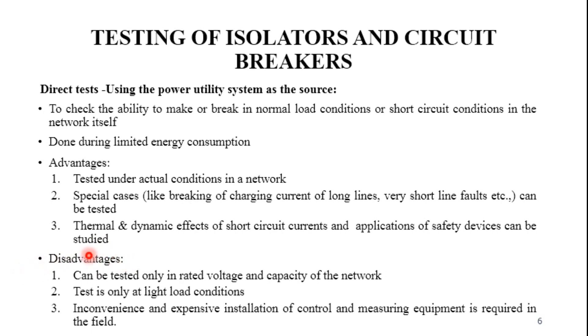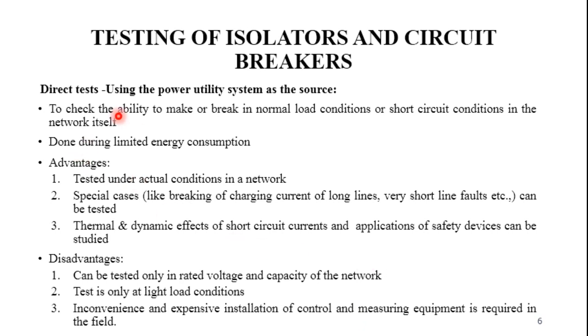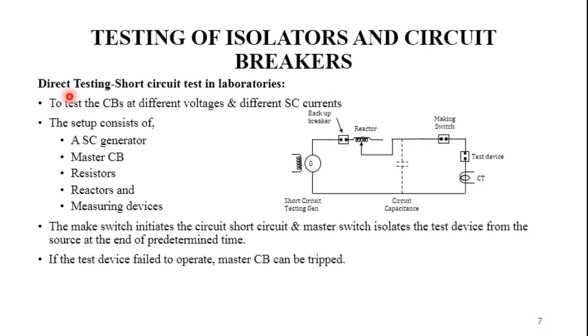Limitations of the direct field test include: testing can only be done at the rated voltage and capacity of the network; the test is done only at light load conditions; and extra inconvenience and expenses in the installation of control and measuring equipment are required to conduct the field test.